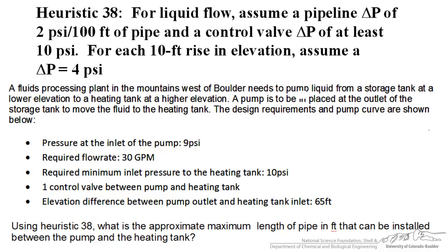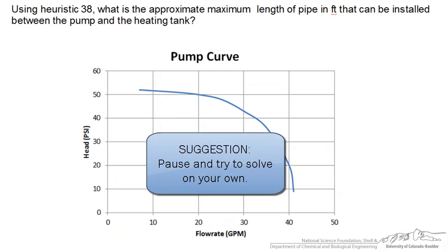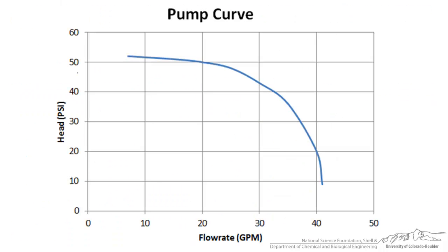The last bit of information you'll need is the pump curve. A pump curve gives you an idea of what the head pressure will be at any given flow rate. In this problem, we're interested in a flow rate of 30 gallons per minute, which means the maximum pressure head we can accomplish with this pump is about 43 psi.